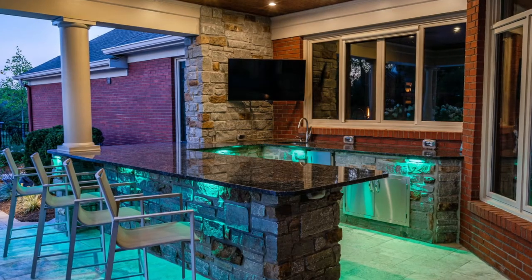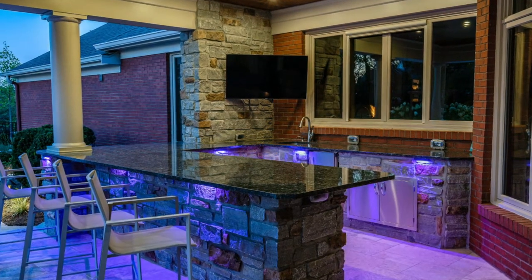And so when Lauren comes to you with a design and she says she wants colored lights everywhere, lit up like Logan Airport, what kind of control do you have over color temperature and the RGB effects of lights now? There's a few companies that are selling what's called integrated LEDs, where you cannot change the lamp, but built in is an adjustable lamp, and adjustable color, and adjustable output. So what they're trying to do is limit the amount of fixtures in the warehouse in the distributors. So you have one fixture, you can turn that Kelvin temperature from 3,000 down to 2,200 or anything in between. You can go from 2 watts to 7 watts, or you can go from 15 degrees to 100 degrees.